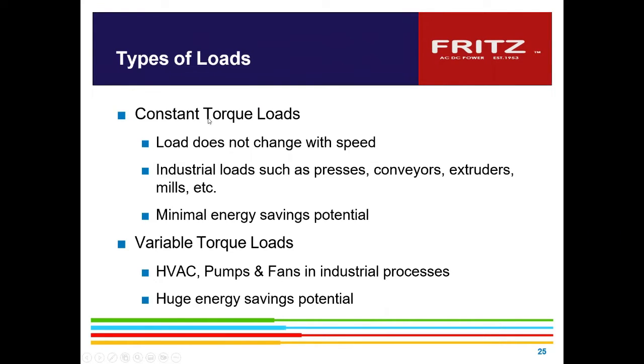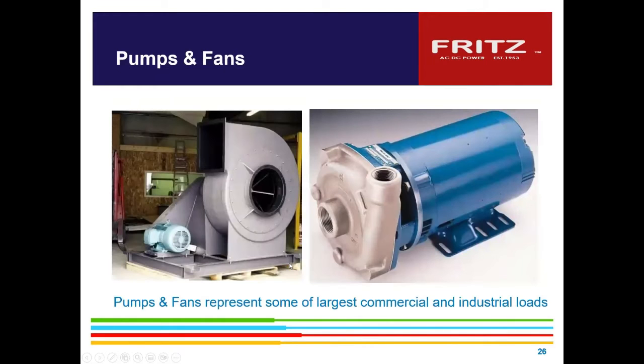So what I was talking about is you've got a constant torque load and then a variable torque load. And what they mean by that is a constant torque load is a load that doesn't change with speed. So it has that same amount of torque requirement to move the materials, but as you speed it up, it increases in horsepower requirement compared to lower speed. So a speed control can help that. The variable torque loads, again, we talked about that already, have the huge savings.